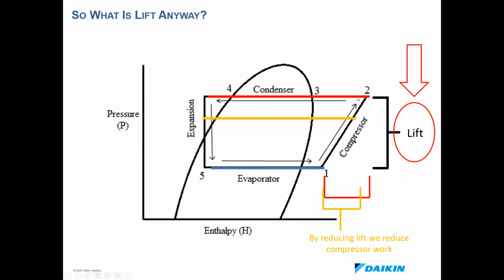And then when the ambient temperature drops, this is your new state point that your compressor needs to work to. It doesn't need to compress the refrigerant all the way to this 2. It can go to just here, to 2 prime. So by reducing this lift, we effectively reduce the compressor work needed to meet that condition. So you can see the difference between H1 and H2 here in red, and then H1 and H2 prime here in yellow. You can see the compressor work is a lot lower. Because of the VVR, we don't have to work as hard to meet that condition.